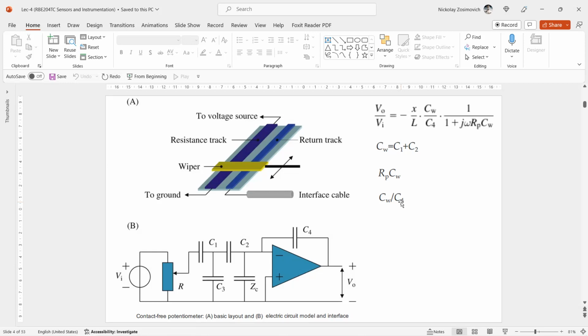Nice. Similar to the conventional types, the nonlinearity of the contact-free potentiometer is determined by the inhomogeneity of the resistance track and is therefore not much better than the traditional type. However, the transfer characteristic is somewhat smoother due to the extension of the floating wiper. Why? Because small location irregularities are averaged out.